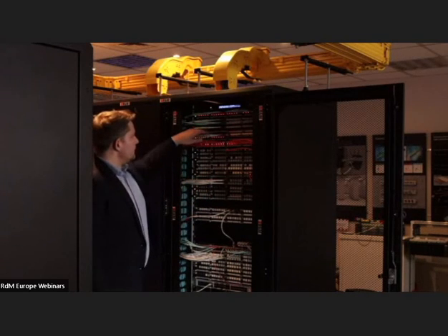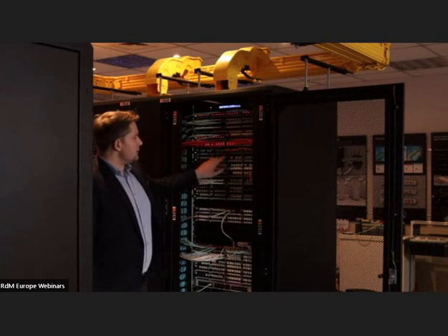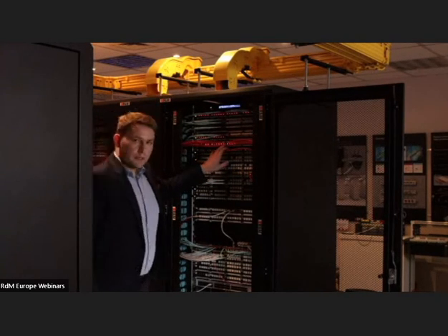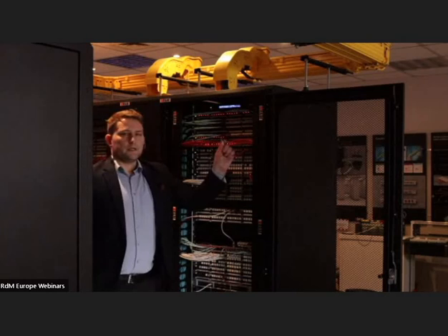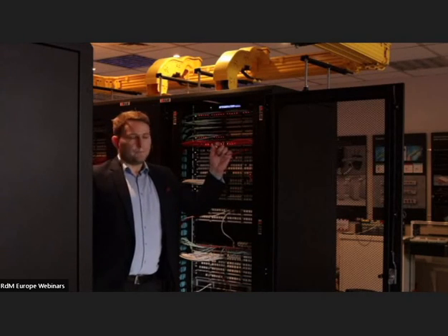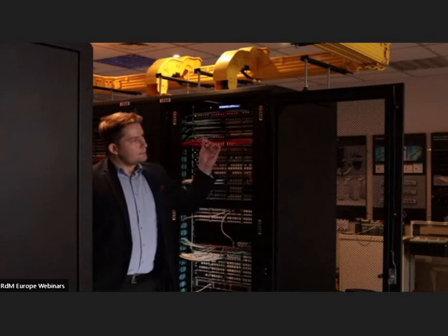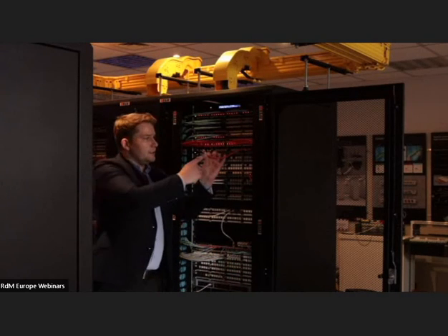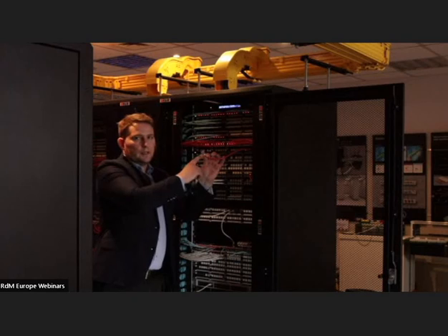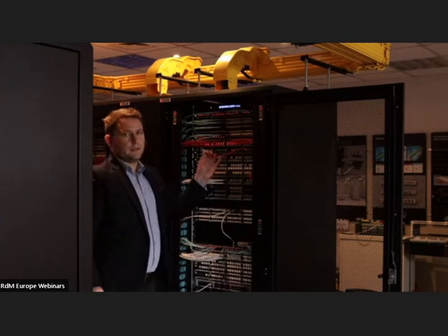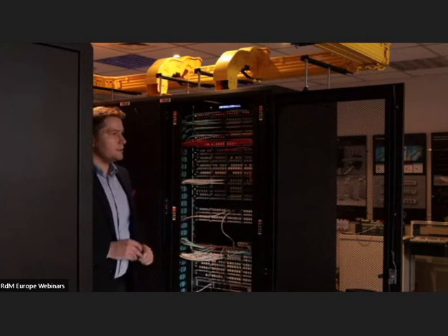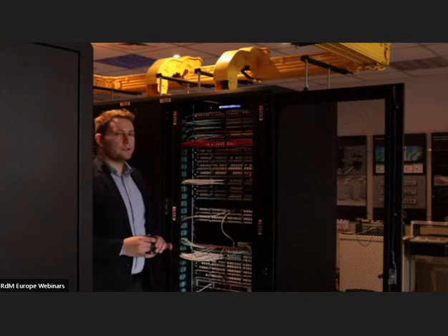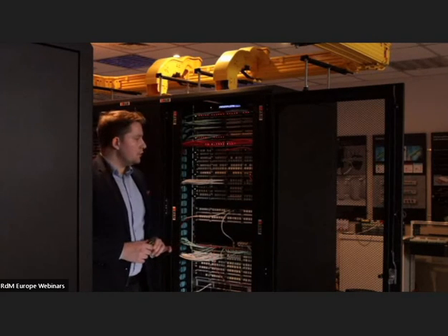And those red lights, which you can observe here, are the lights coming from sensor bars, and sensor bars are detecting RFID tags which are on the patch cords. This is what I showed you before on the slide. Here you can see, maybe not so clearly, but this gray plastic has an RFID tag inside.